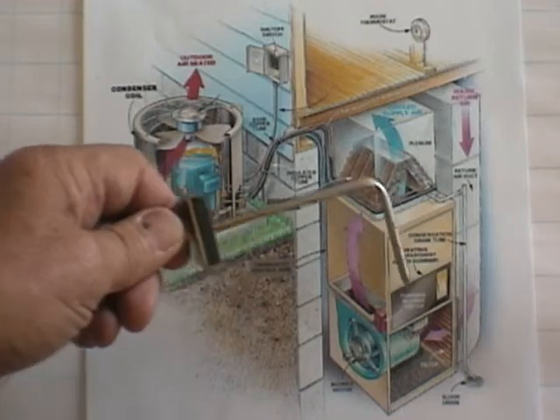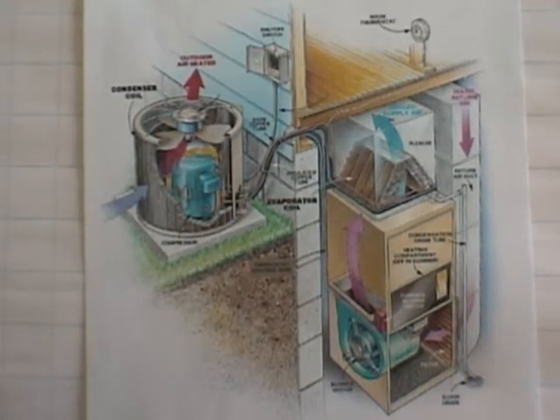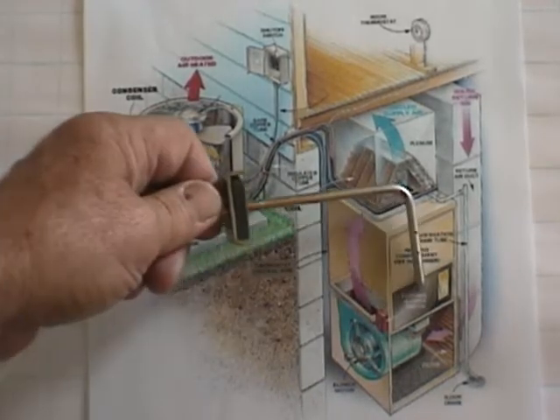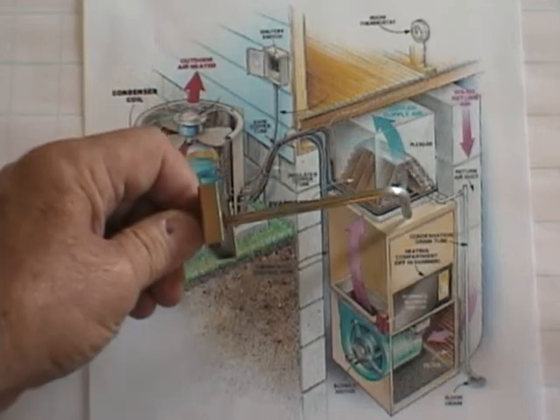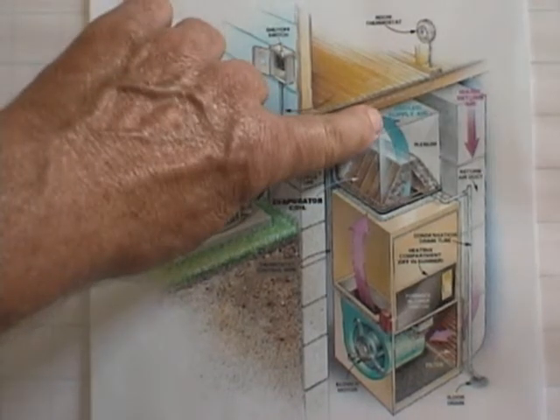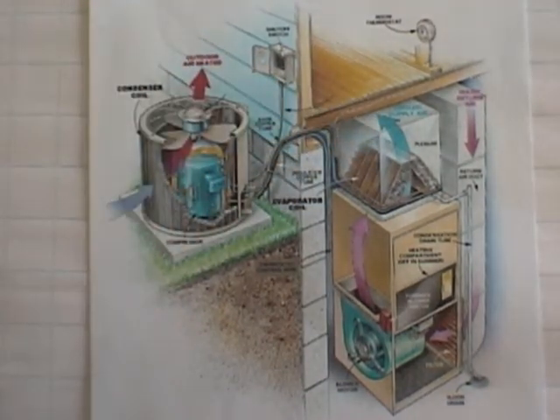If we wanted to check the pressure drop across a coil and compare it to published data for this coil, then of course we would put one probe in below the coil and one probe in on the discharge side of the coil. You want to get these probes in areas where there's as little turbulence as possible to get a good reading. You might have to try 2 or 3 locations to get a good idea of where that might be. Again, you can do some exploratory probe searches to determine what those areas are.